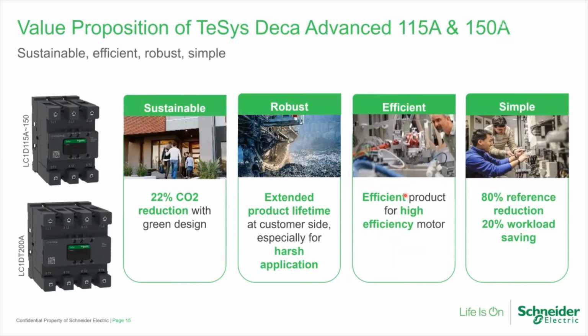As a Schneider value, we always say that we value what we say, and hence with all these features we can very well say that this contactor is completely designed taking sustainability into consideration. So 22% CO2 reduction can happen by using these contactors. These contactors are more robust because we have been designing this contactor for use in harsh applications. These are more efficient. We saw that these are tested for IE3, IE4 motors and simple to use. It has front access, plus a lot of references are reduced from 225 to 24.